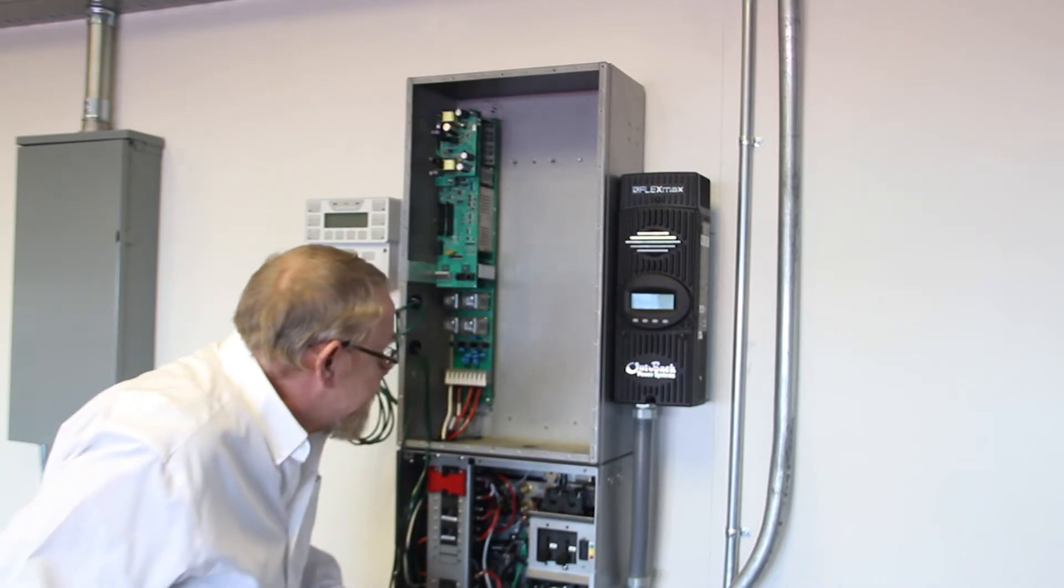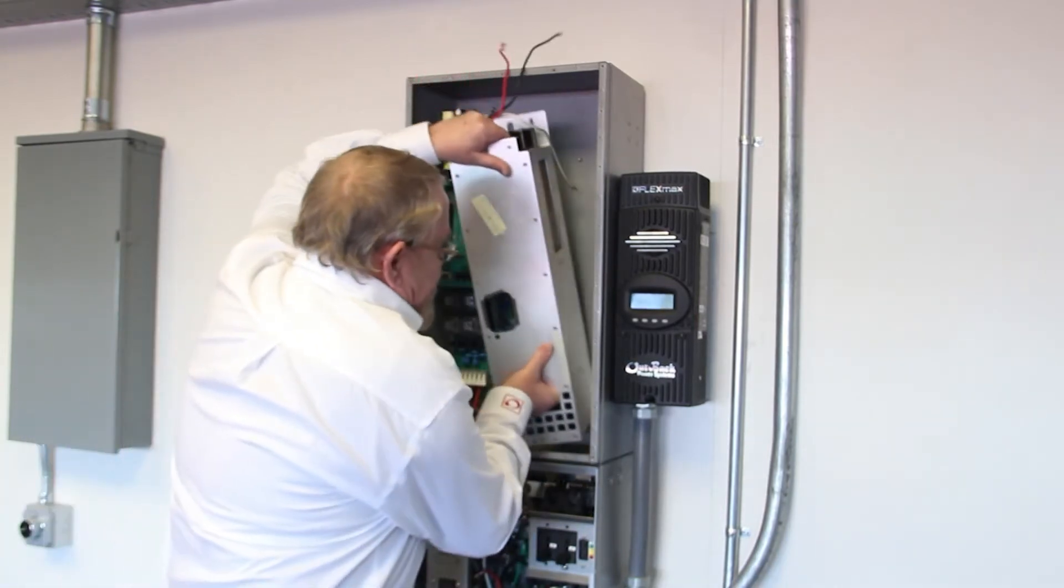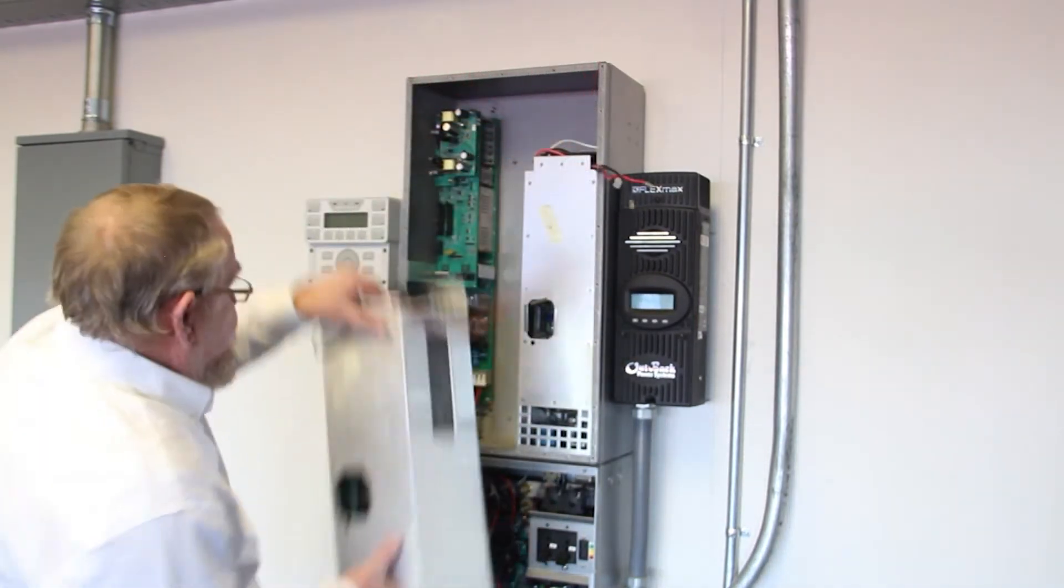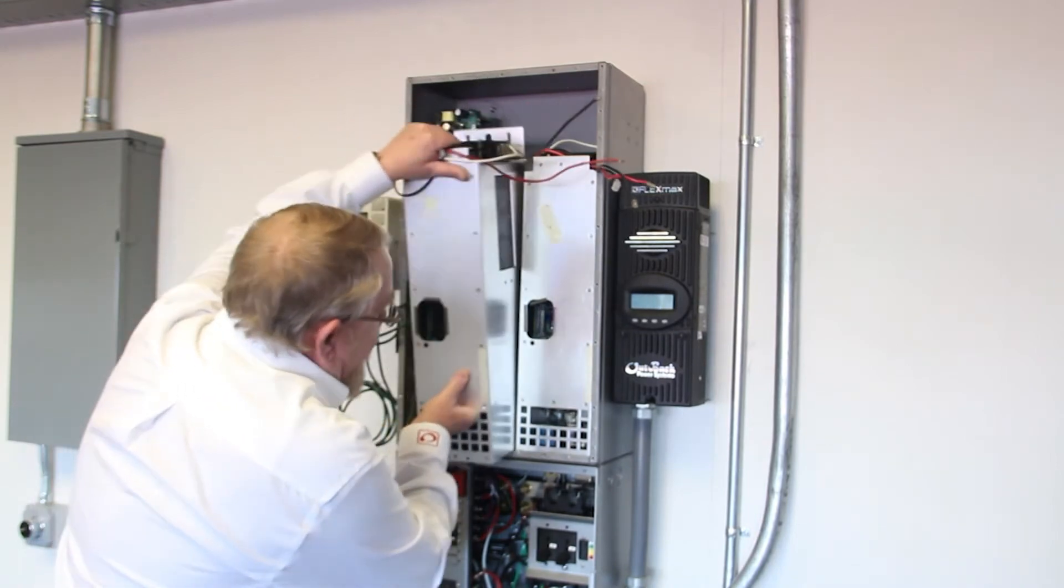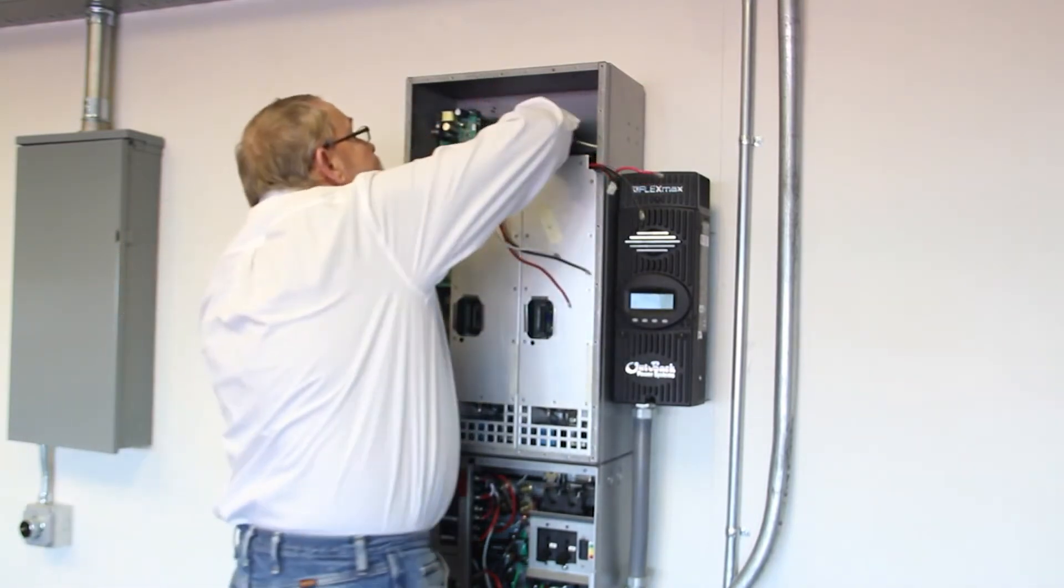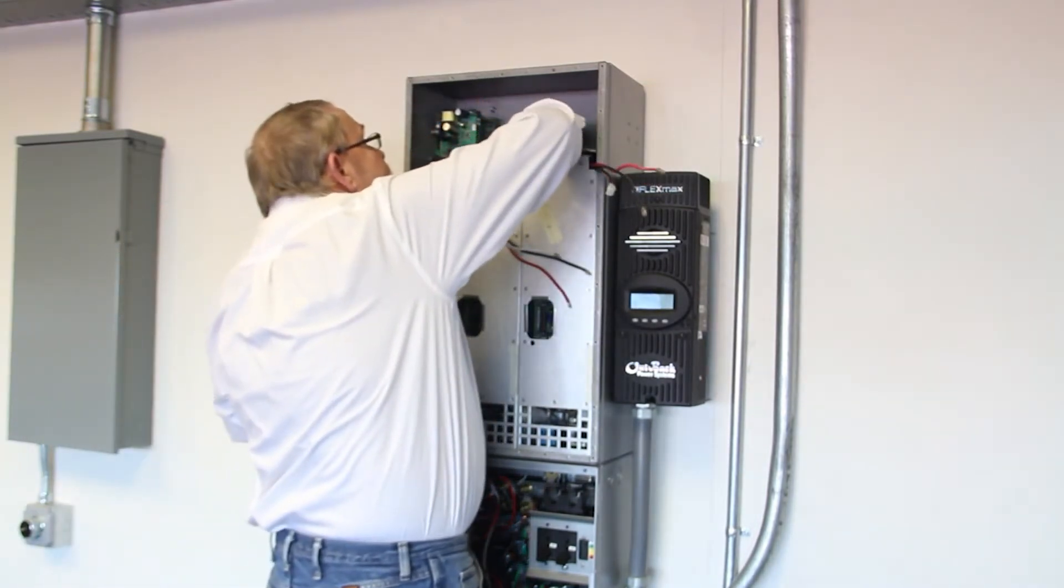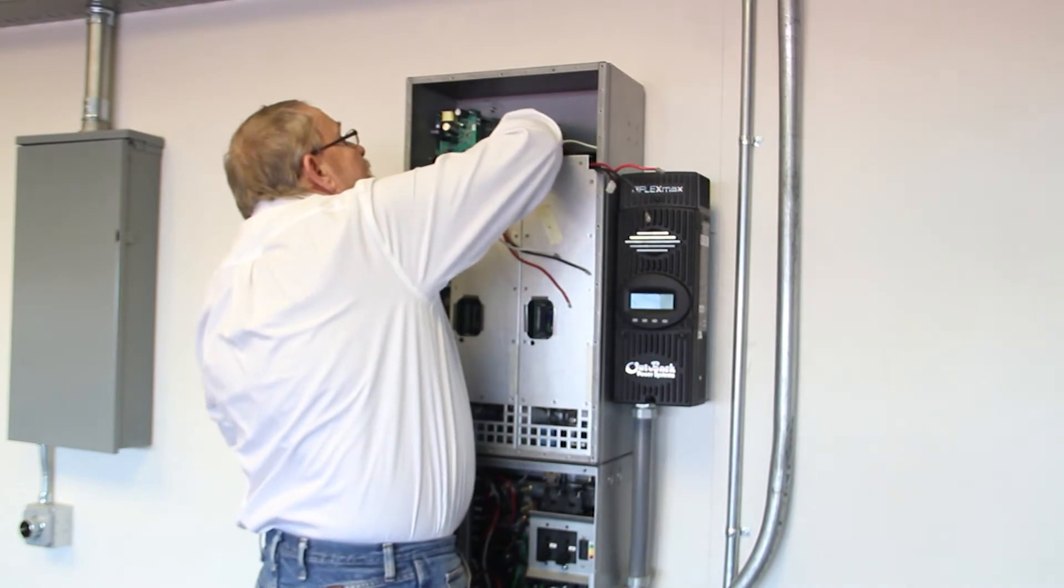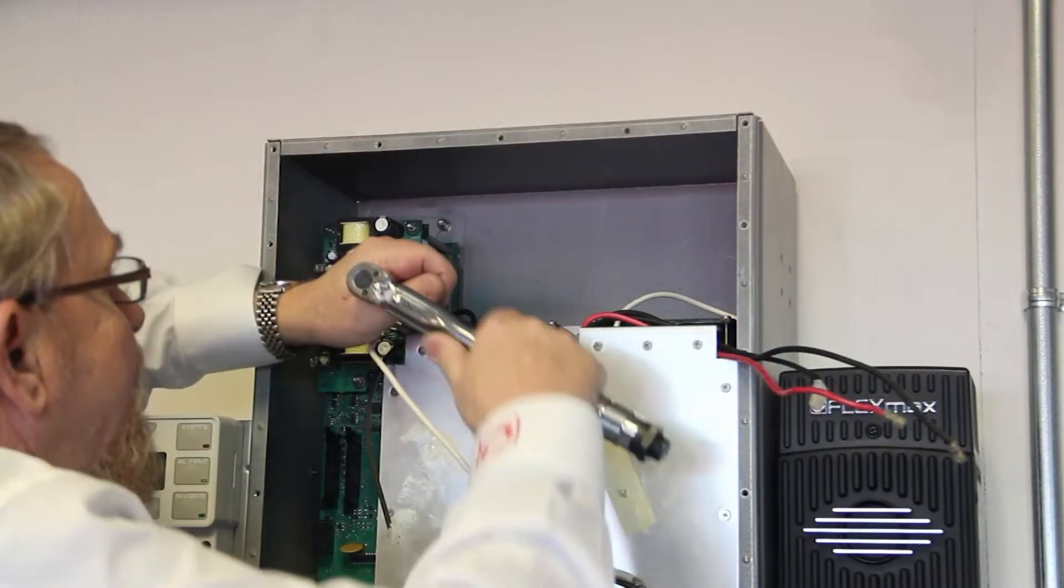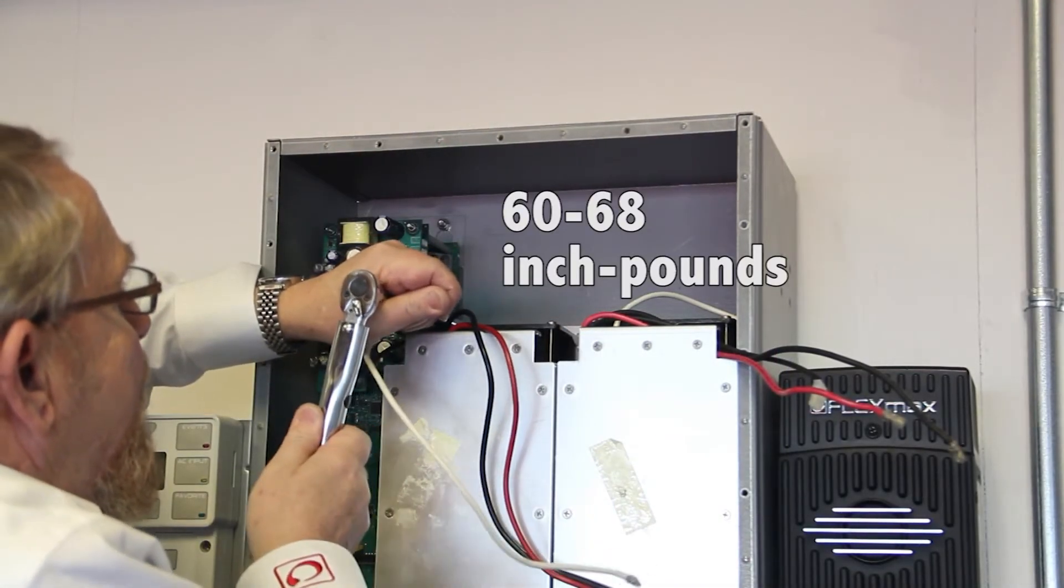Insert the two power modules into their designated spots. Replace the two upper 10mm nuts on each power module and torque to a value of 60 to 68 inch pounds.